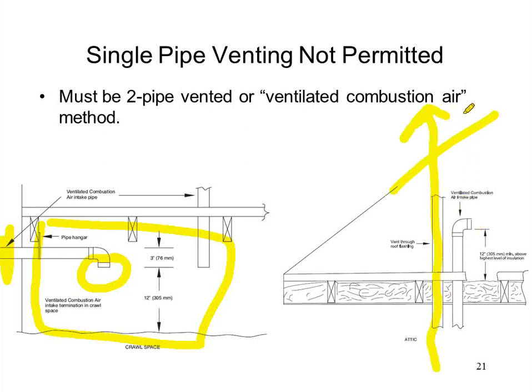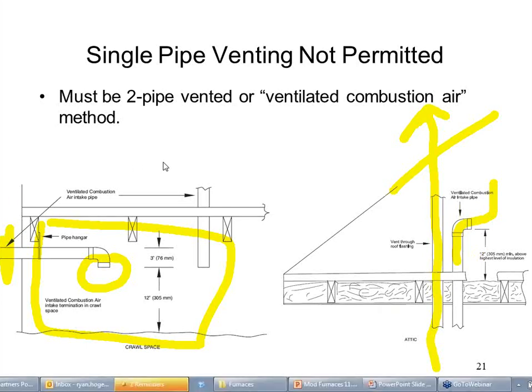And then my combustion pipe, instead of bringing it from fully outdoors, I can bring the combustion air from the attic itself, assuming that the attic is ventilated as well. So I can do 2-pipe, where I have the pipes going fully outside, or I can do ventilated combustion air, which is kind of like single pipe, but I'm not stealing from the space. I'm stealing from a ventilated space, like the ventilated crawl space or ventilated attic. This is a little different than some of the non-modulating units that you've probably worked on from Bryant and Carrier that do allow single pipe.